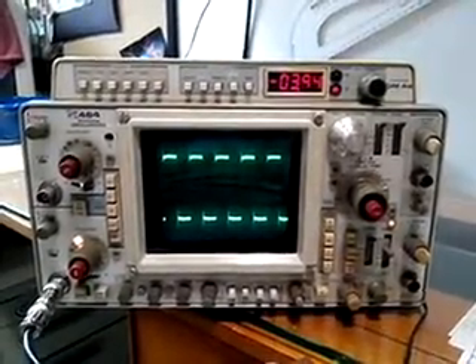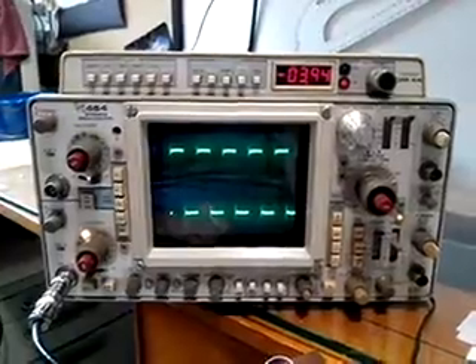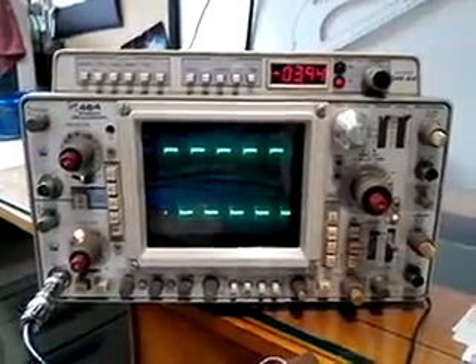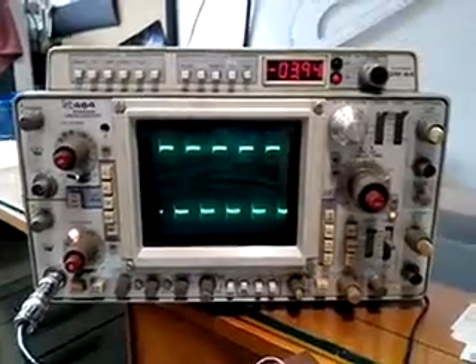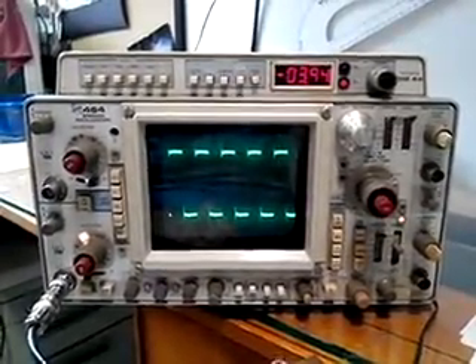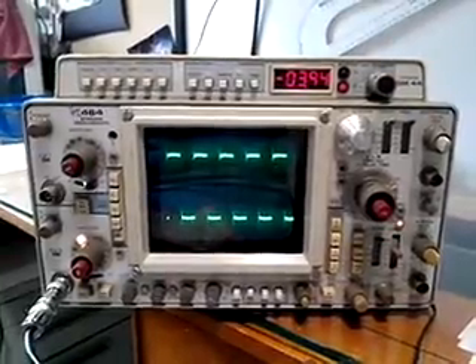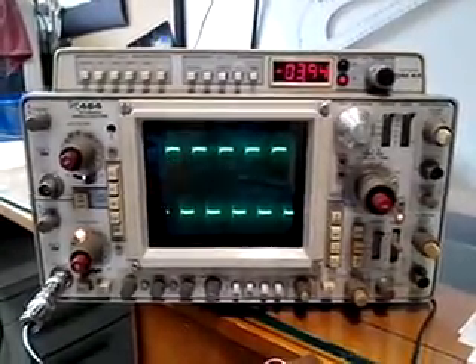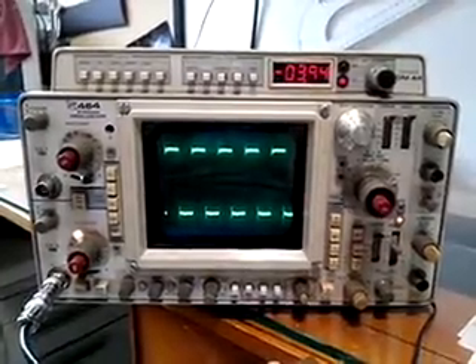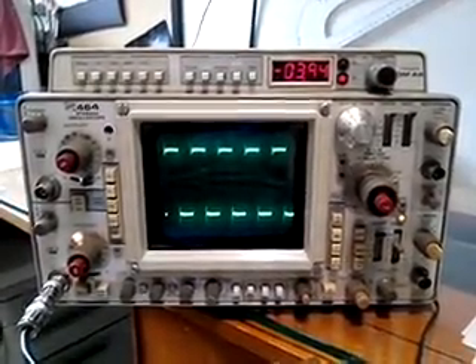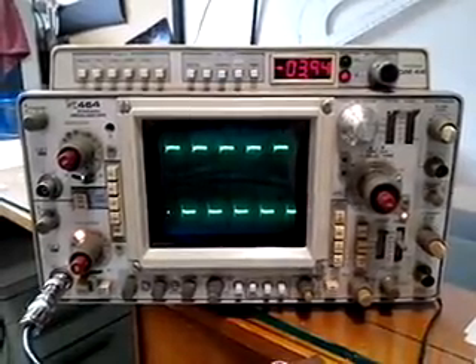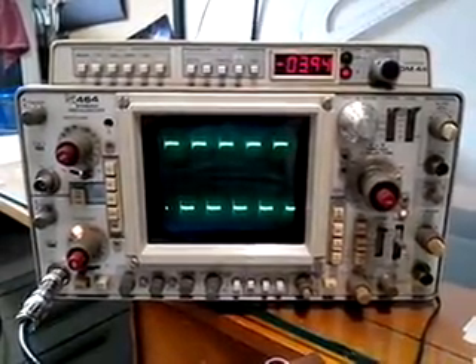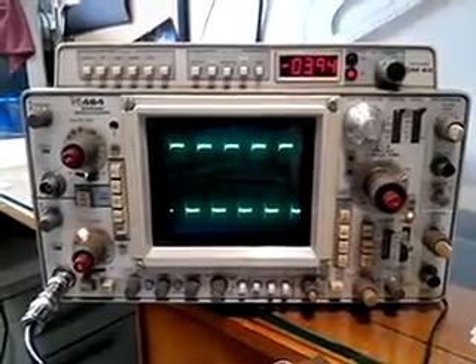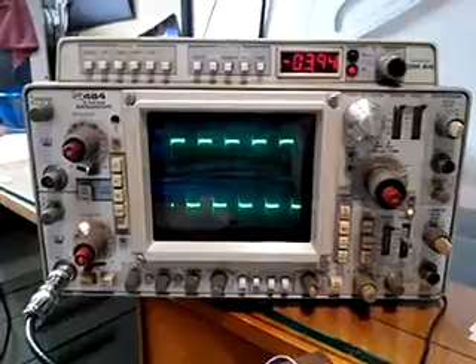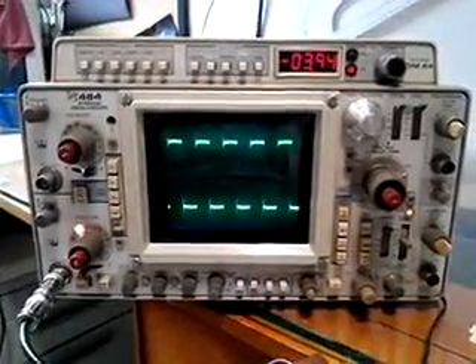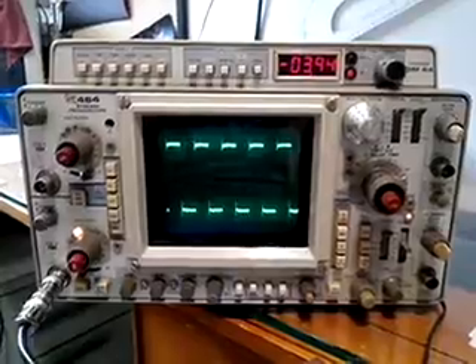Okay, so here is the Tektronix 464 I have acquired a month ago or so. Since then I have been dealing with the problem in the high voltage inverter, which was failing after warming up, and indeed I had to replace the high voltage transformer. And yes, after replacing the high voltage transformer, the high voltage is now stable. I can run the oscilloscope for whatever time I want.